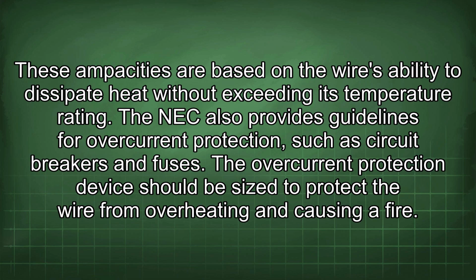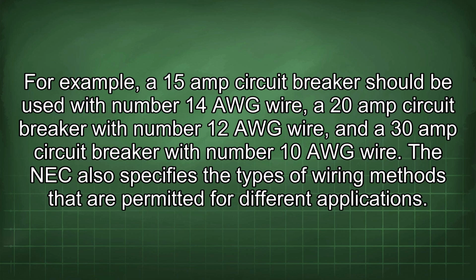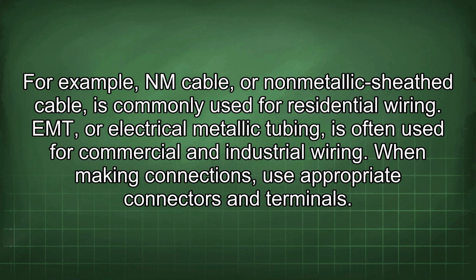The NEC also provides guidelines for overcurrent protection, such as circuit breakers and fuses. The overcurrent protection device should be sized to protect the wire from overheating and causing a fire. For example, a 15 amp circuit breaker should be used with number 14 AWG wire, a 20 amp circuit breaker with number 12 AWG wire, and a 30 amp circuit breaker with number 10 AWG wire. The NEC also specifies the types of wiring methods that are permitted for different applications. For example, NM cable or non-metallic sheath cable is commonly used for residential wiring. EMT, or electrical metallic tubing, is often used for commercial and industrial wiring.